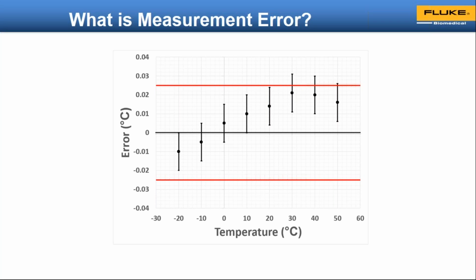But with the uncertainty bands, you see that it's very clear to us that we're already outside the testing limits when we consider the uncertainty of measurement. And that means that we absolutely should be doing something about probably the last 4 measurements all the way to the right. Definitely at least those last 4, to make sure that they are inside the tolerance band, the pass-fail criteria. In fact, whenever possible, we really want that to be more central, at the midpoint on that data plot. And we probably will make a calibration adjustment in order to bring that back in where we need it to be, so that if there's any drift in the interim between when we made the measurement and the next time we make the measurement, it's still going to be inside the acceptable limits.